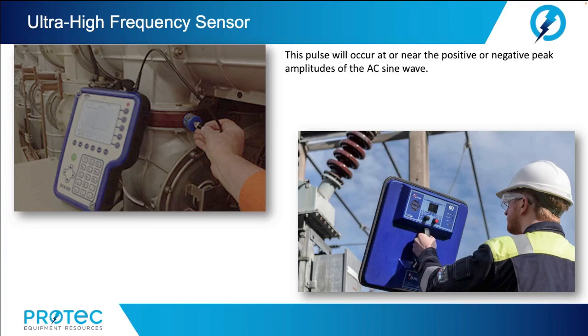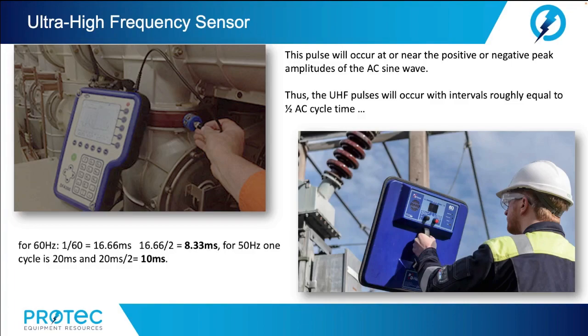The pulses will occur at or near the positive or negative peak amplitudes of the AC sine wave. Thus, the UHF pulses will occur with intervals roughly equal to 1/2 the AC cycle time. Now, for 60 Hz, 1 divided by 60 equals 16.66 milliseconds. 16.66 milliseconds divided by 2 would be 8.33 milliseconds. And for 50 Hz, 1 cycle would be 20 milliseconds. 20 milliseconds divided by 2 would be 10 milliseconds.